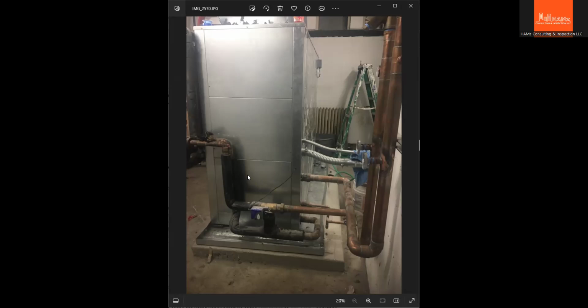But in this case, we are testing it at an acceptable pressure. So I think the equipment could handle the pressure, but it does not necessarily need to be included in the test, just in case, because if anything happens to this equipment, it's going to be the contractor's fault. They need to replace it if they ever broke it. If the pressure is too high and the equipment cannot take it, it might have a problem inside of the unit. So that's an extra precaution for the test.